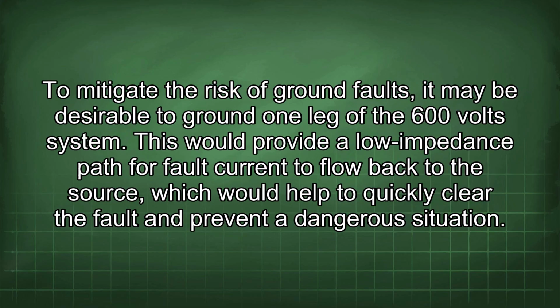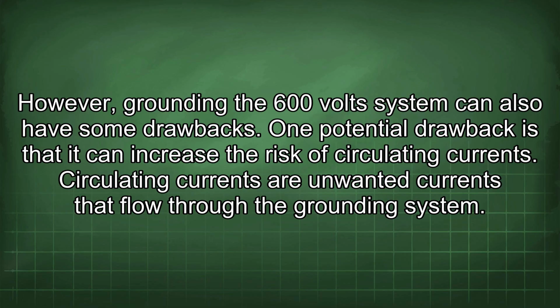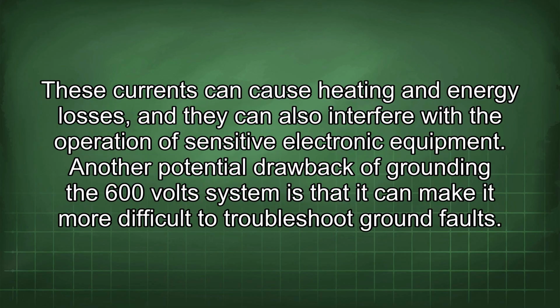To mitigate the risk of ground faults, it may be desirable to ground one leg of the 600-volt system. This would provide a low impedance path for fault current to flow back to the source, which would help to quickly clear the fault and prevent a dangerous situation. However, grounding the 600-volt system can also have some drawbacks. One potential drawback is that it can increase the risk of circulating currents. Circulating currents are unwanted currents that flow through the grounding system. These currents can cause heating and energy losses, and they can also interfere with the operation of sensitive electronic equipment.